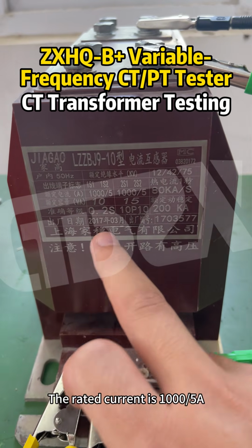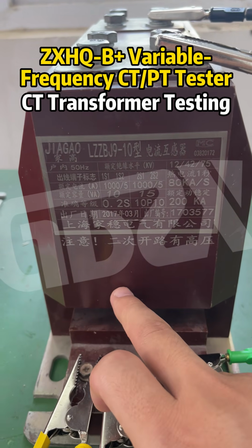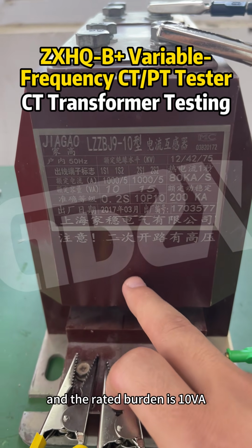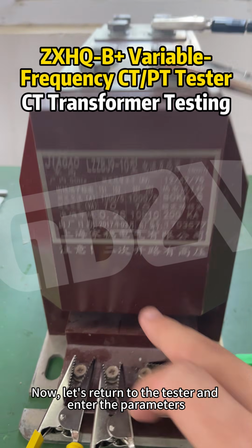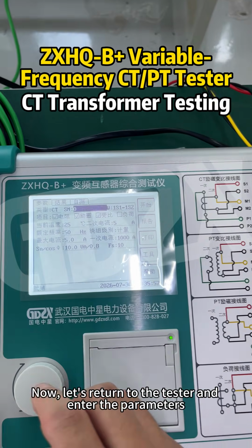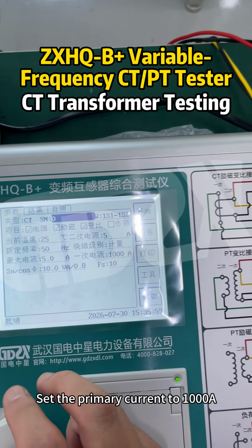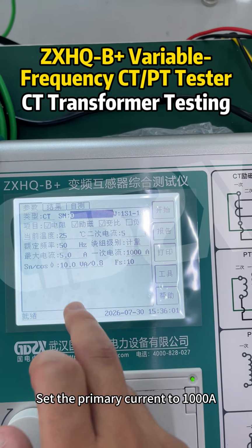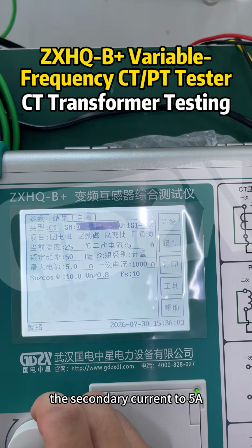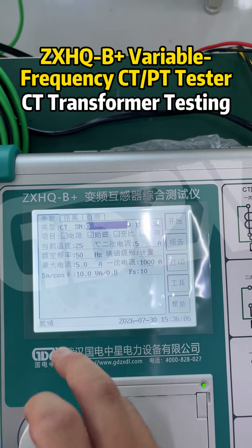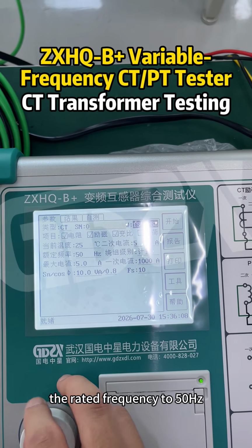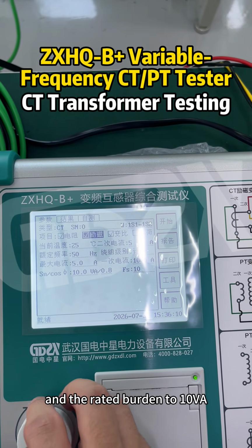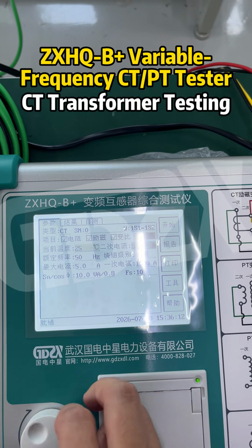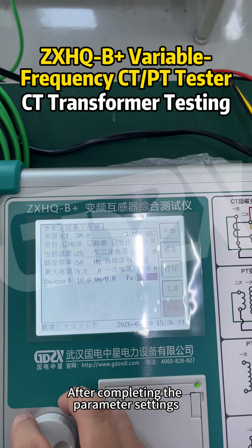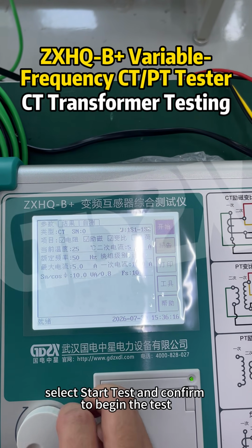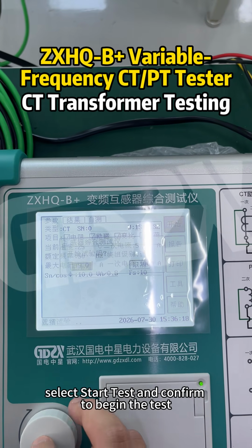The rated current is 1000/5 A, and the rated burden is 10 VA. Now, let's return to the tester and enter the parameters. The rated current is 1000/5 A, and the rated burden is 10 VA. Set the rated frequency to 50 Hz, and the rated burden to 10 VA. After completing the parameter settings, select Start Test and confirm to begin the test.